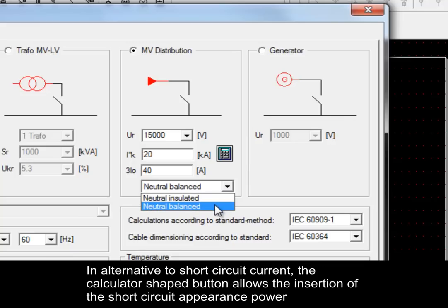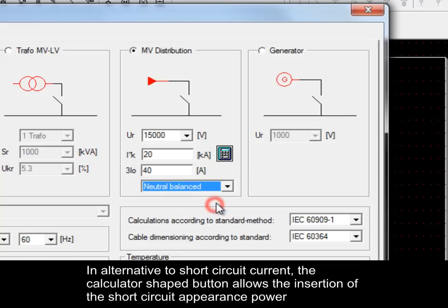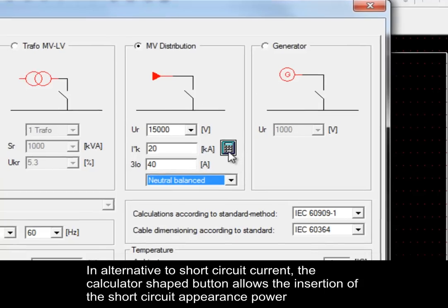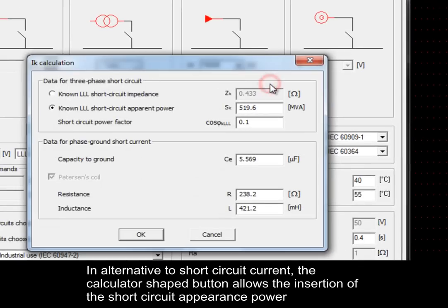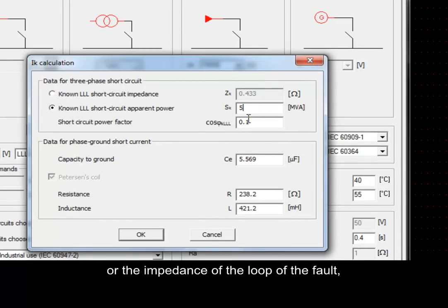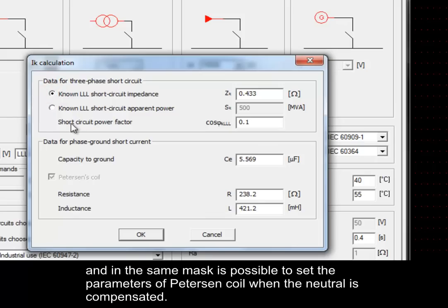In alternative to short circuit current, the calculator shaped button allows the insertion of the short circuit apparent power or the impedance of the loop of the fault. And in the same mask, it is possible to set the parameters of Petersen coil when the neutral is compensated.